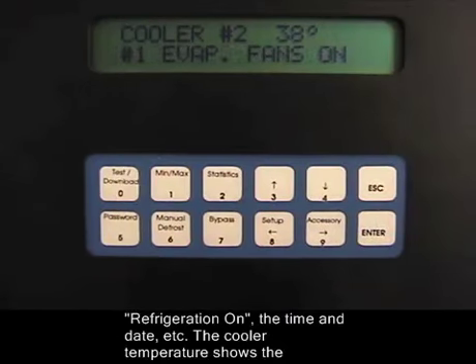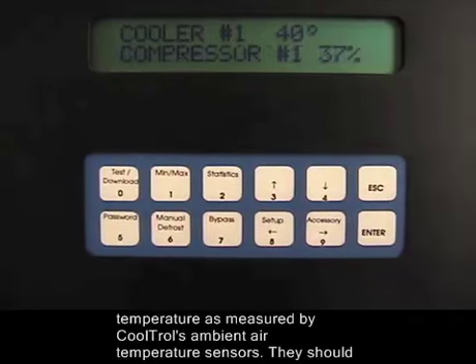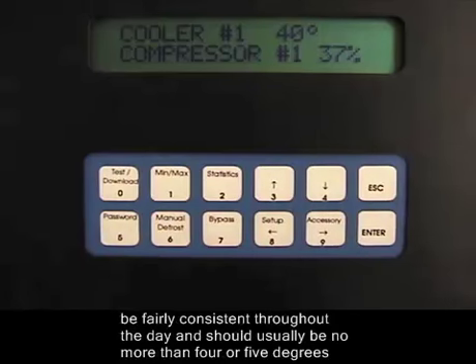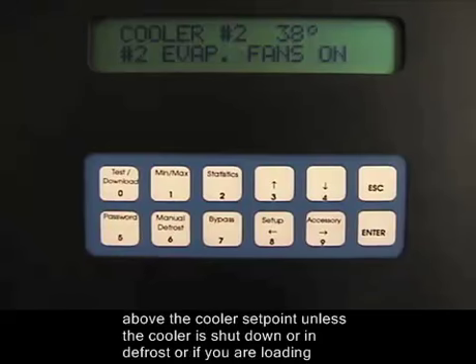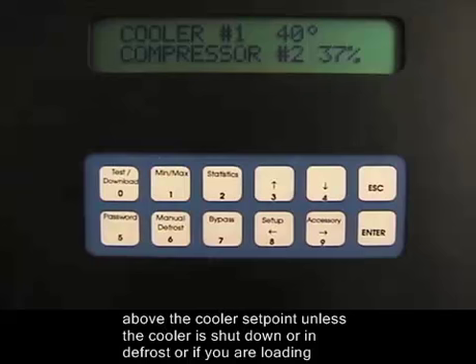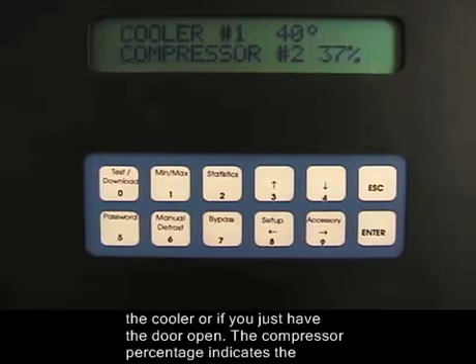The cooler temperature shows the temperature as measured by CoolTrol's ambient air temperature sensor. It should be fairly consistent throughout the day and should usually be no more than 4 or 5 degrees above the cooler's set point, unless the cooler is shut down or in defrost, or if you are loading the cooler or just have the door open.